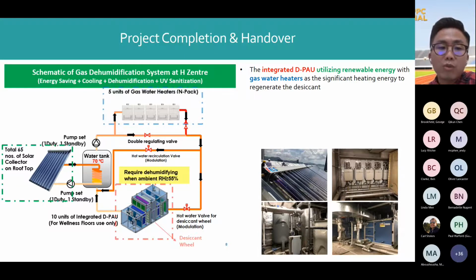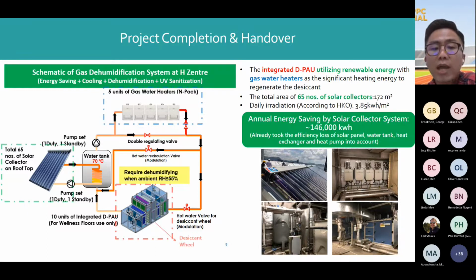The hot water then transfers to the 10 integrated PAUs for the desiccant wheel regeneration only when the ambient relative humidity is equal to or above 55%. If the ambient relative humidity is below 55%, the hot water circuit will bypass the integrated PAU and go back to the water storage tank for reserving the hot water. The annual energy saving by the solar thermal panels is around 146,000 kWh, which already took the efficiency loss of the equipment into account.